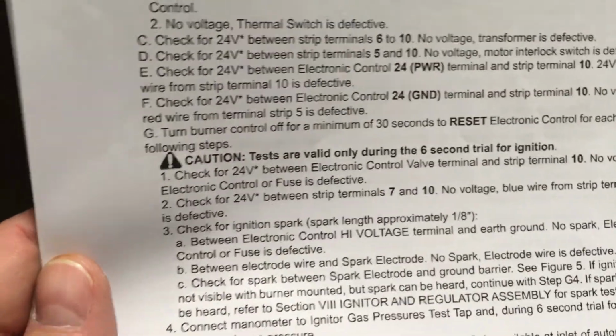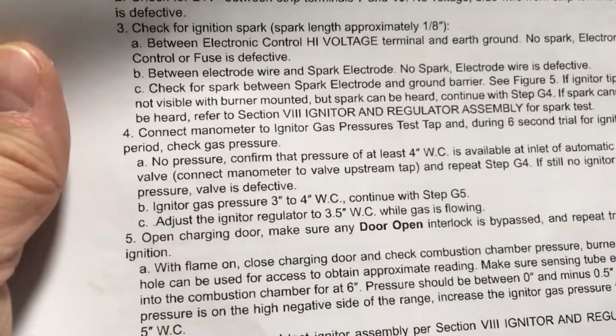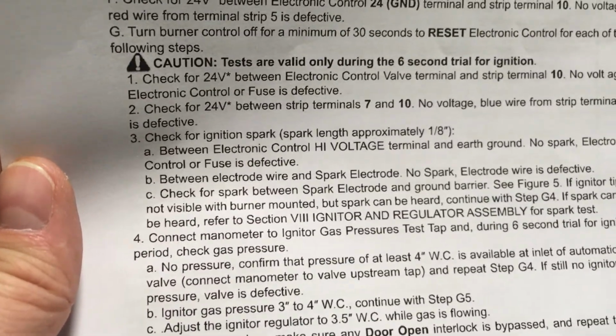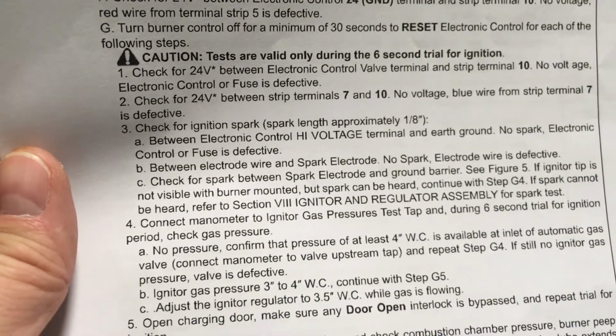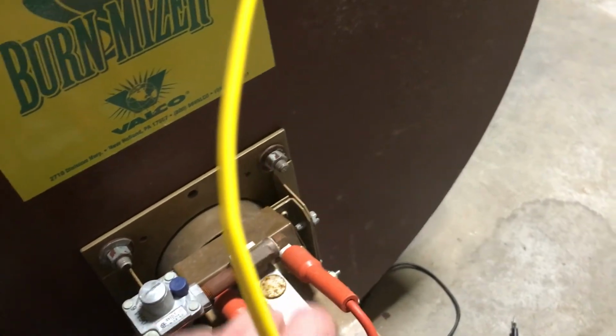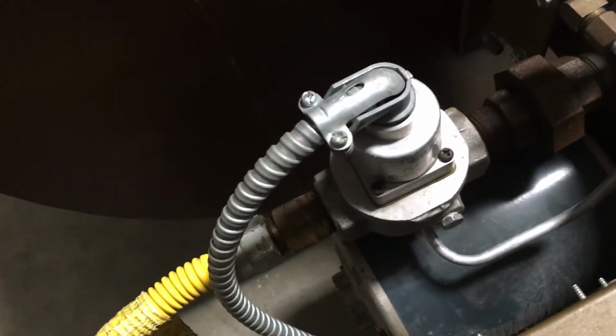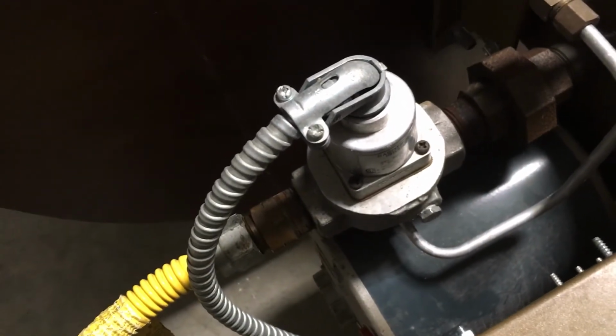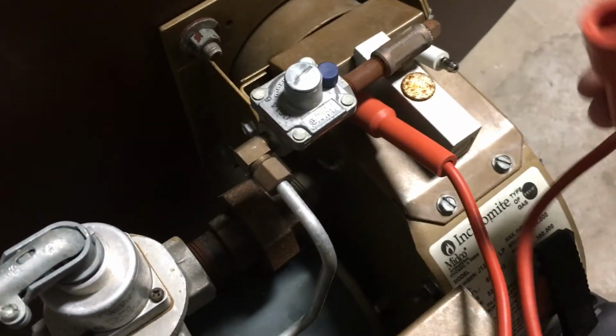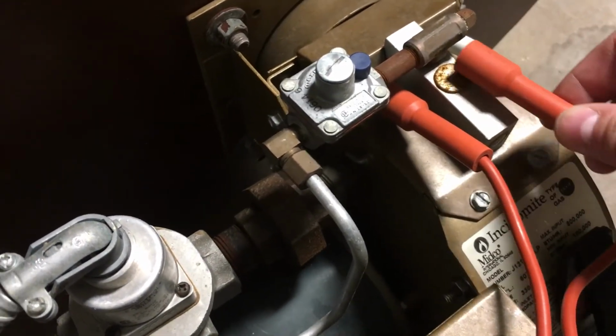If you go through this, you can see in step 4, and you can go through this and you see step 3 where it says check for ignition spark, where the spark is approximately 1/8 inch long, a gap. You want to verify spark voltages or the actual spark itself through the cables and the igniter. You can do that, although you really can't see that much here with the rubber boot on it, so you can't really get much of a gap.